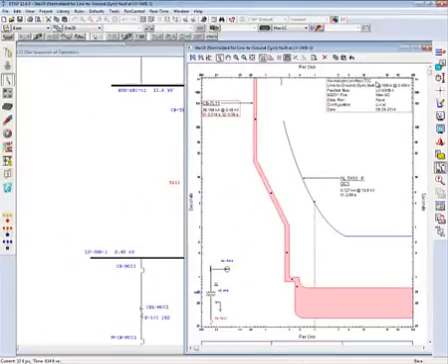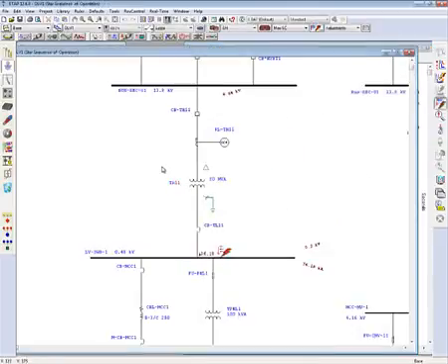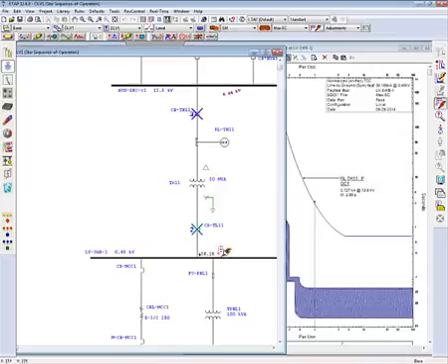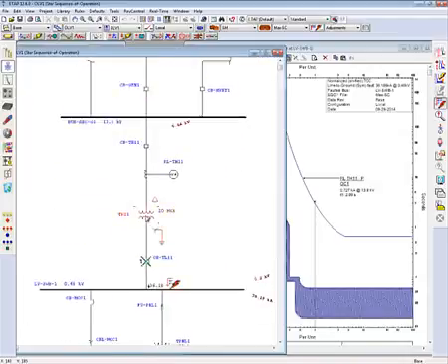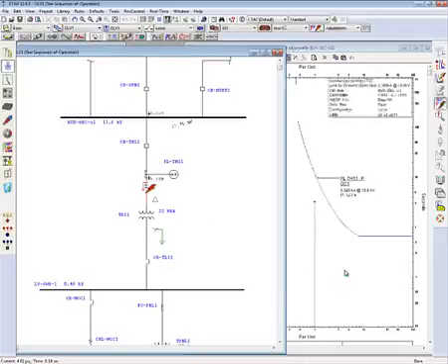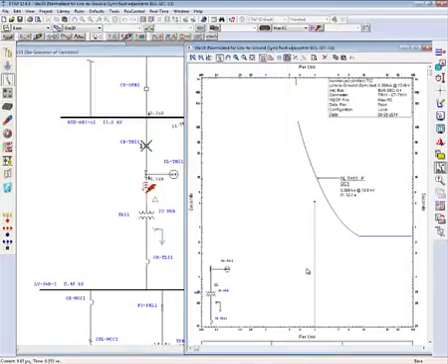One of the major advantages of doing this in ETAP is that a fault can be placed at any location. So if I move my fault from downstream to upstream of the transformer, I can observe that the curves are shifted on the star view, as CBTL11 does not see any through fault current in this case.